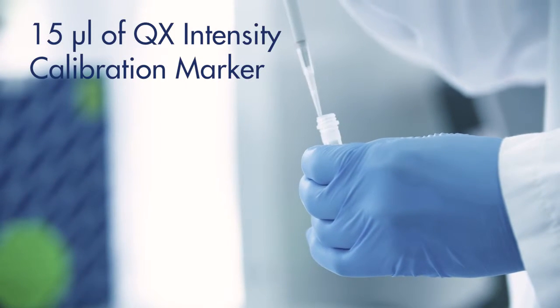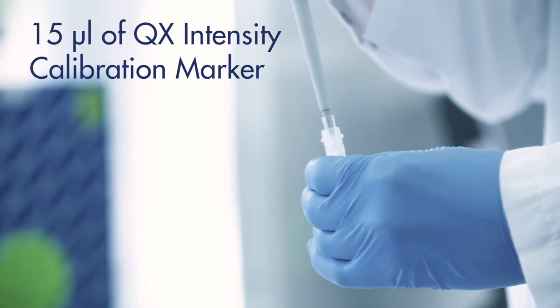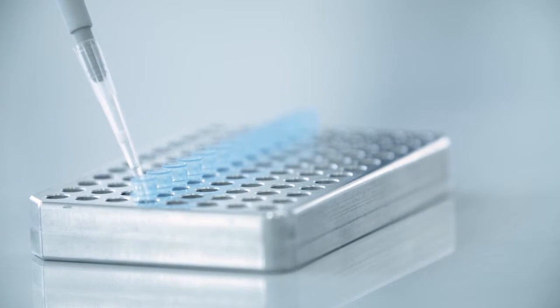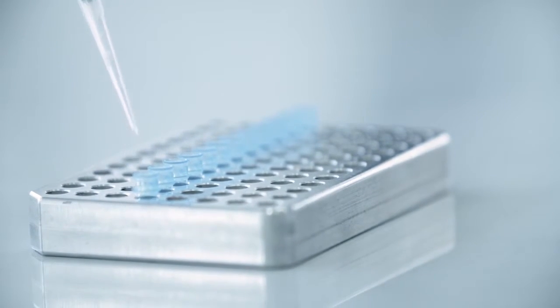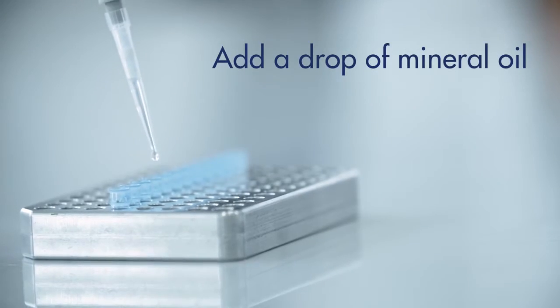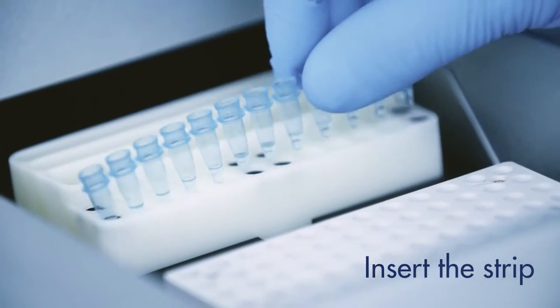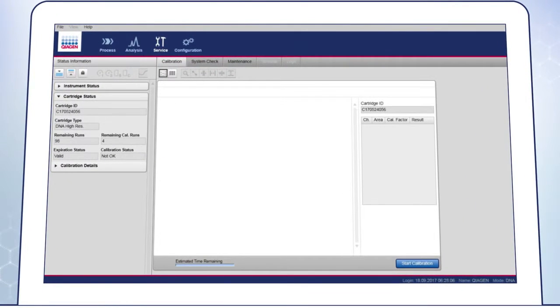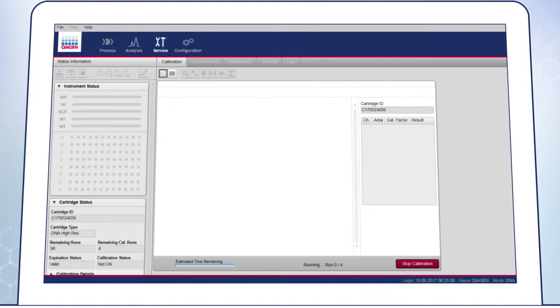Load 15 microliters of QX intensity calibration marker into a 0.2 milliliter 12-tube strip. Add a drop of mineral oil and insert the strip into the marker 2 position of the buffer tray. To launch the calibration run, go to the service environment of the QIAxcel ScreenGel software. Go to the calibration screen and click on Start Calibration.